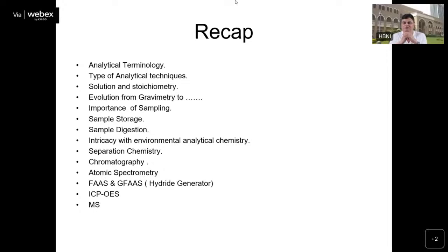This is especially true when we are analyzing various kinds of biological fluids, because many doctors are interested to know the heavy element concentration in biological fluids taken from the patient. In that case, graphite furnace is very useful because the volume requirement may be about 10 microliters, which is not possible in the case of flame AAS.